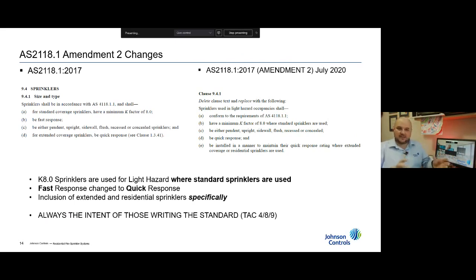So the idea here was never to remove the ability to use residential sprinklers. It was never the intent. It's the way it's been interpreted. So that allows us to use standard listed residential sprinklers in the first place. The second big thing is that any reference to fast response, part B, has been changed to quick response. So that tidies up a bit of that confusion.